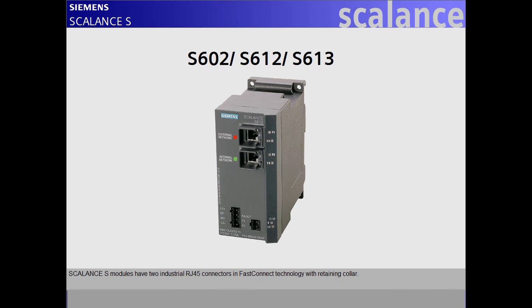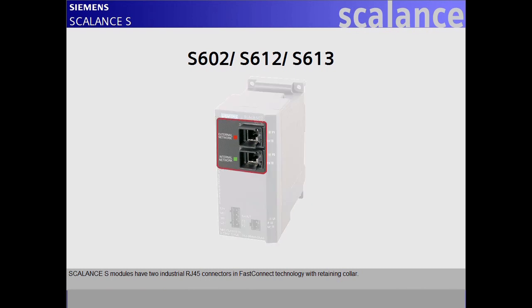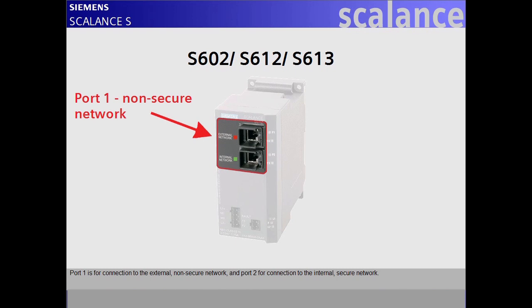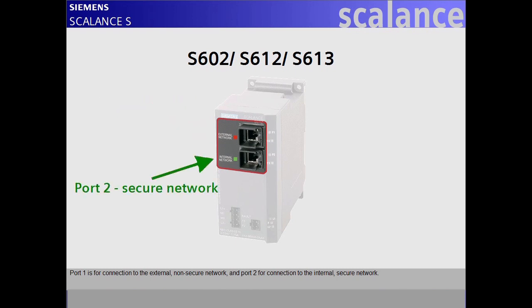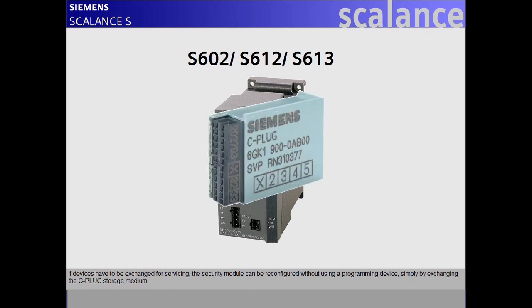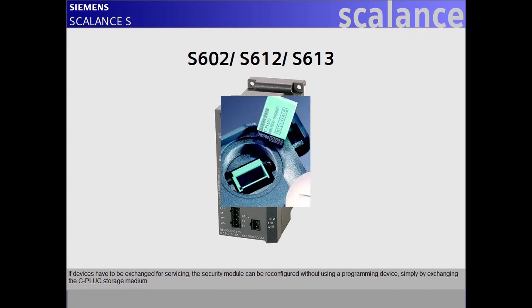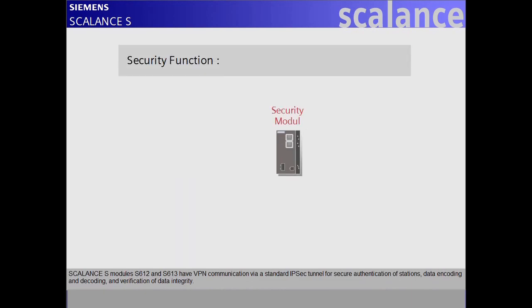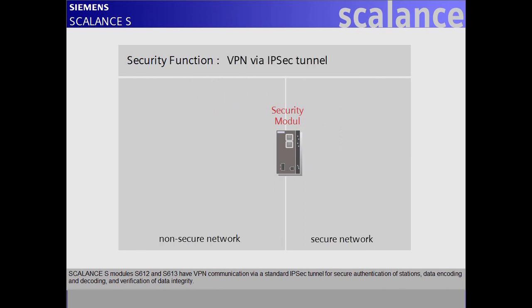Scalance S modules have two industrial RJ45 connectors in FastConnect technology with retaining collar. Port 1 is for connection to the external non-secure network, and port 2 for connection to the internal secure network. If devices have to be exchanged for servicing, the security module can be reconfigured without using a programming device, simply by exchanging the C-plug storage medium.